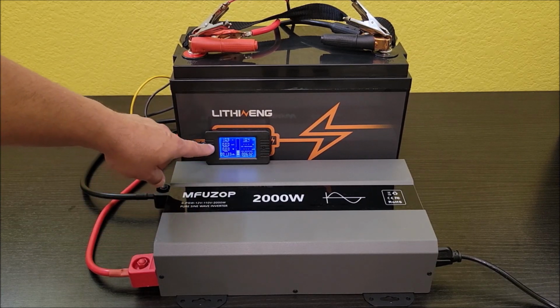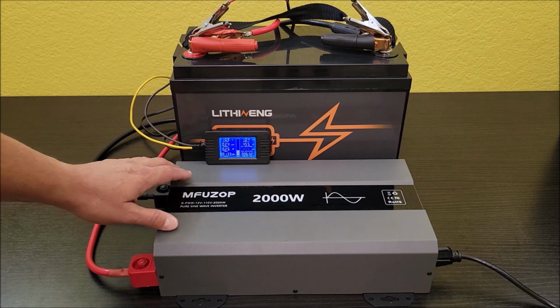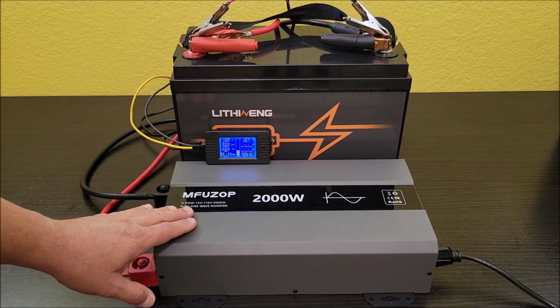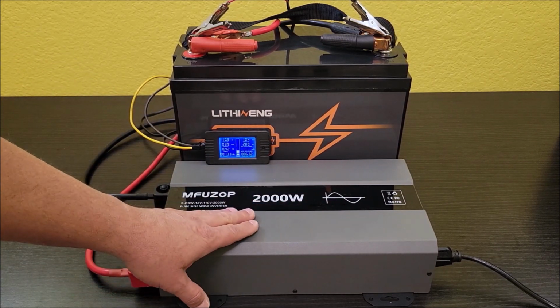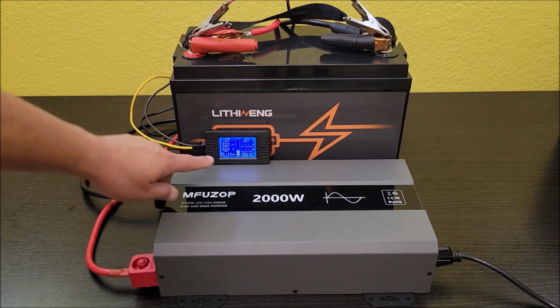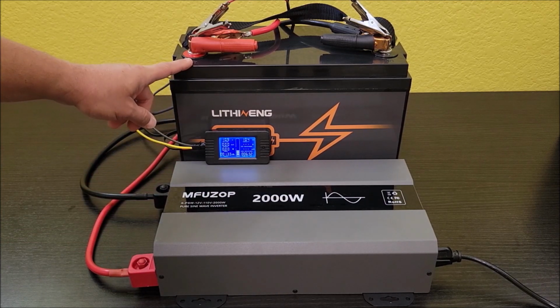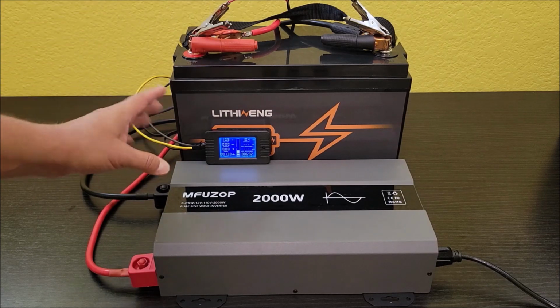Now, that's going to be different than what this says, because it's converting the power through and putting a load on it internally. So this is typically going to read a lower voltage than basically reading right off the terminals. Plus you've got the cabling and resistance and all that.